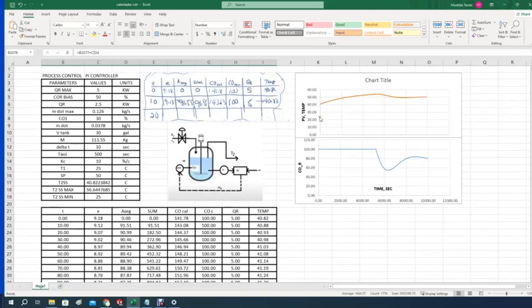Now, this is the story. Here we have the PV value of temperature. I started around 40, 40.82 here, and it went up to 53 or so, and then it dropped and then went up until eventually it's going to get to the 50, no question asked. This is the COR, or the signal from the TIC, so it stayed at 100 even when this was way above the 50 mark here. But then eventually it realized that it was way too high, and it dropped to start to get to a kind of steady state value, and it will stay there until this hits the 50.